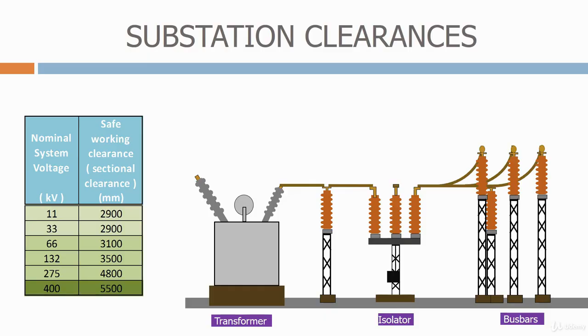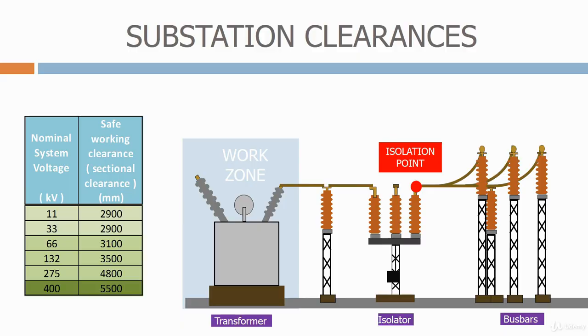Here we have a typical substation with a transformer, an isolator, and a set of bus bars. When we're designing the layout of a bay, we need to think about how we're going to maintain the equipment. Let's imagine we need to work on the transformer. Firstly, we define a safe work zone for the transformer. We then identify the nearest live conductor to the work zone. As the isolator is open, this is on the right-hand side of the isolator, which is the conductor permanently connected to the live bus bar. This is defined as the isolation point. The minimum distance from this point to the work zone should be greater than the safe working clearance. So for 66 kV, the minimum distance should be 3.1 meters.